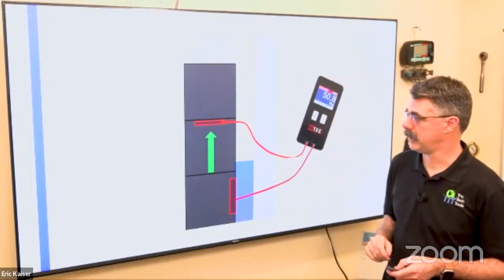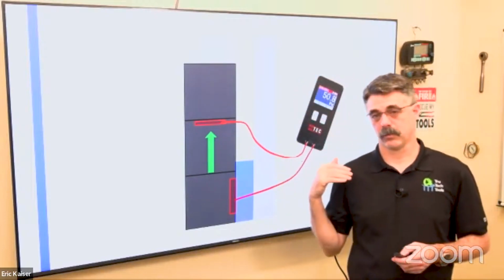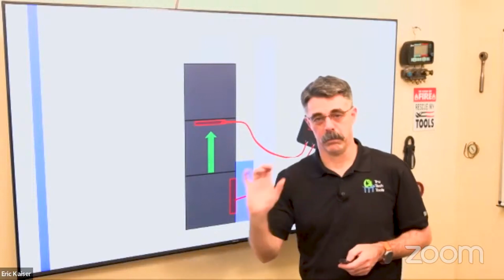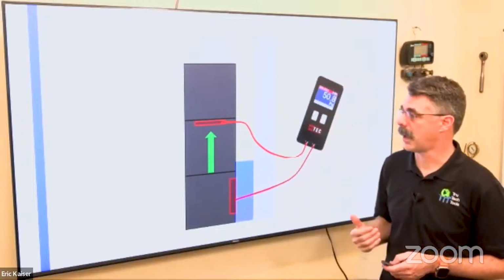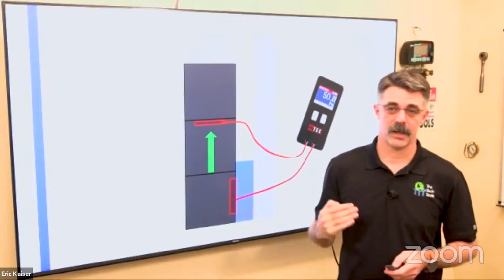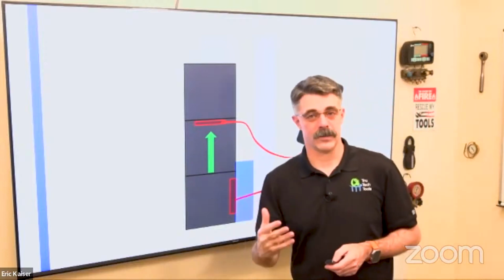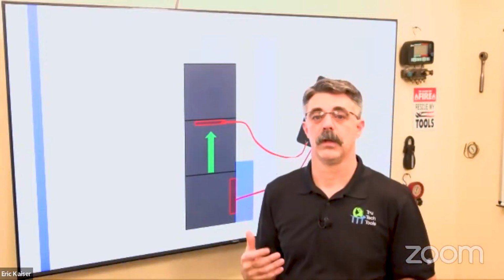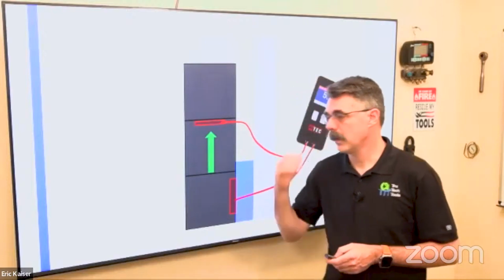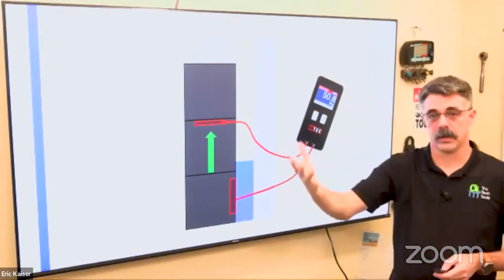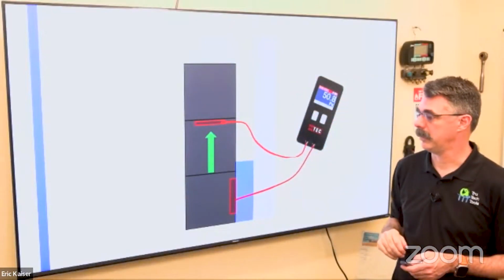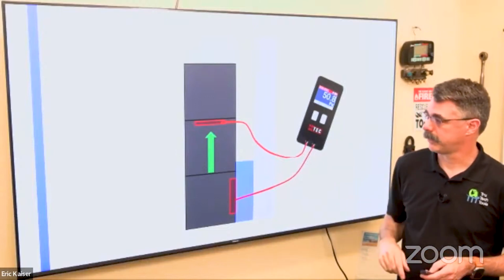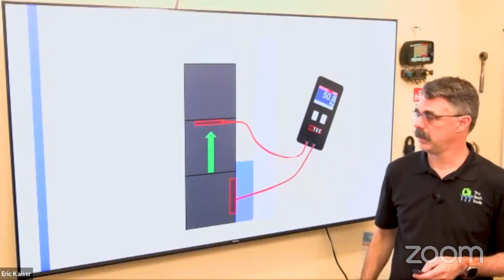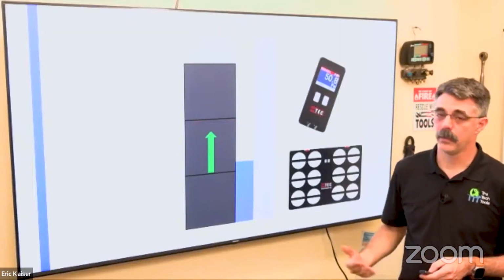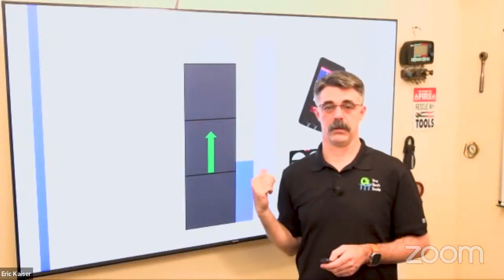You put it in there very intentionally. So that big rush of air, that big hot air coming in there, can create a lot of comfort issues. So downsizing equipment, right-sizing it to the house, can help a lot. And we want to make sure that the ductwork is going to be able to handle that equipment. So static pressure first, external static pressure on the unit, right? And then we want to measure airflow across that unit.